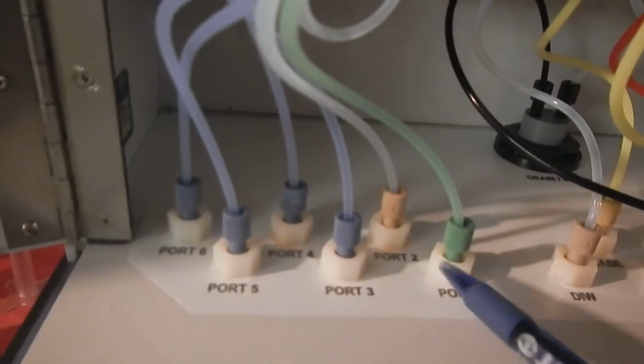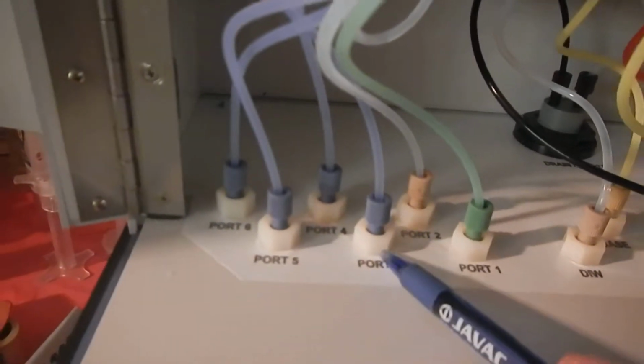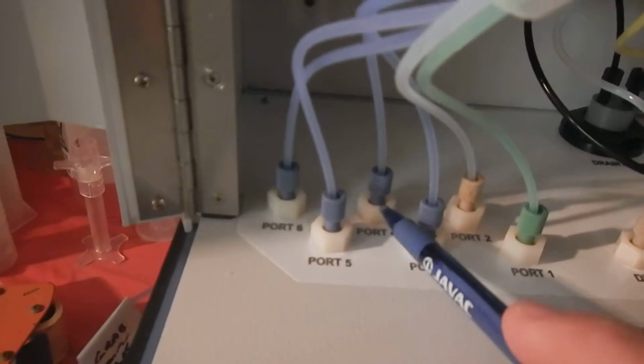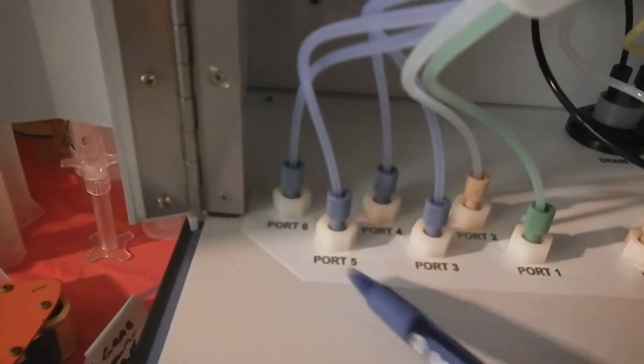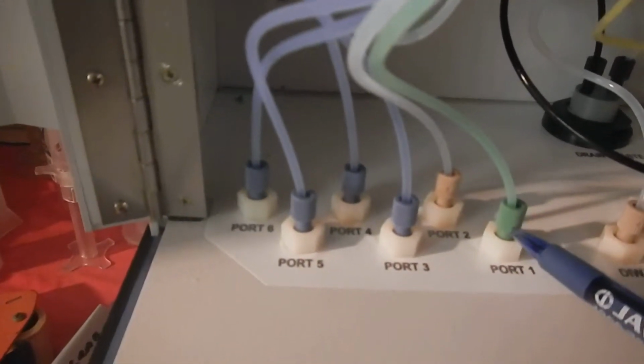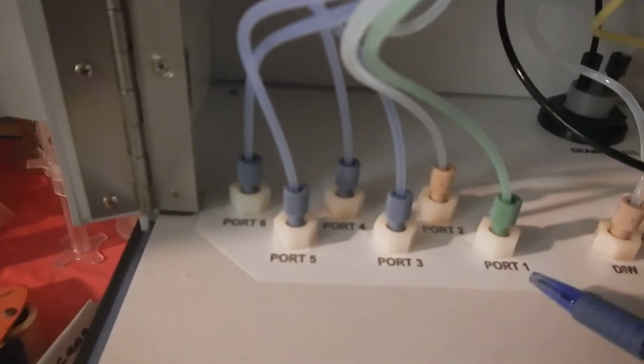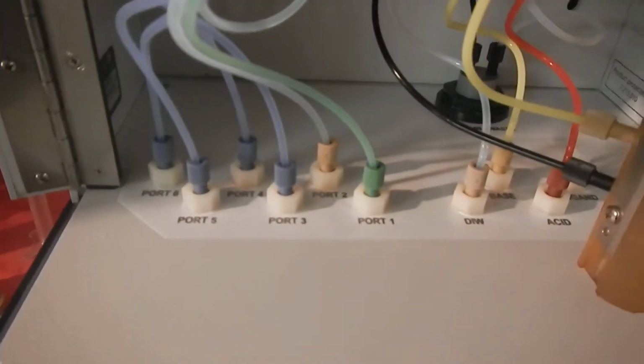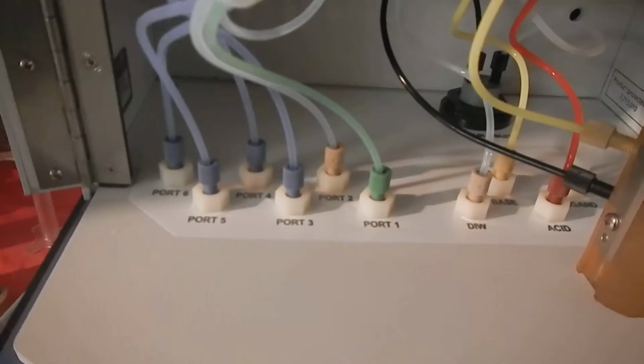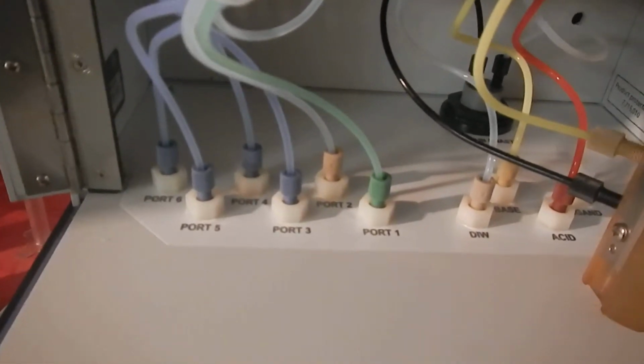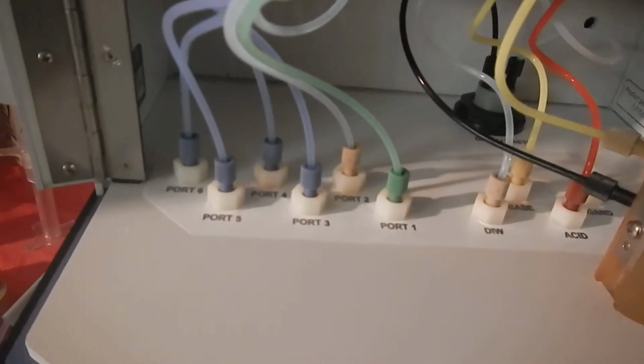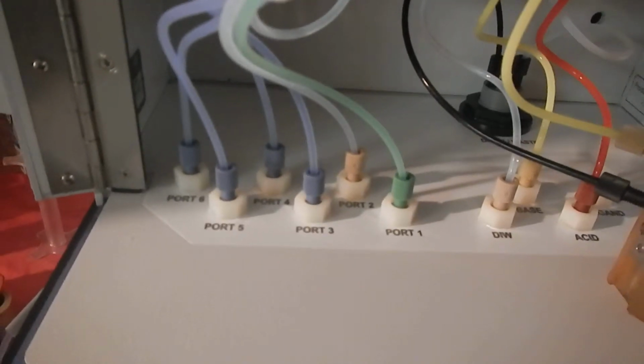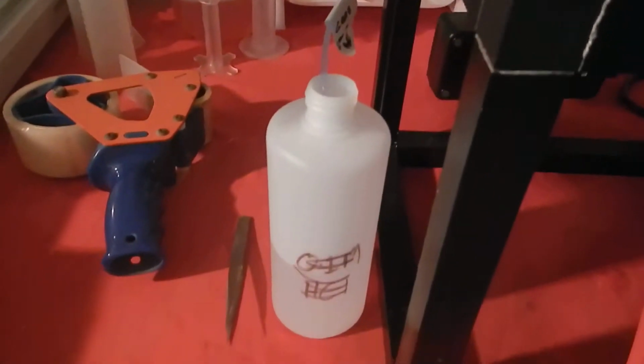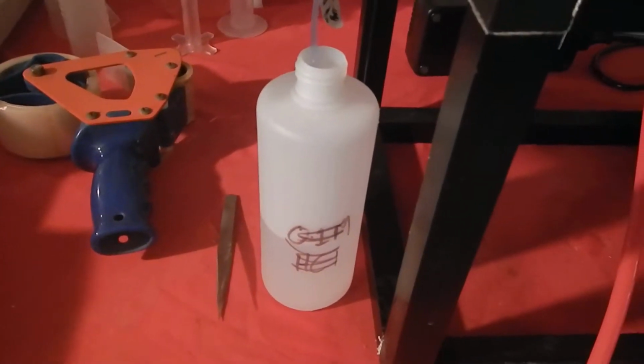Port 1 is standard 1, port 2 is standard 2, port 3 is sample, and in this case port 4 we've got as a grab sample. There are two free ports which can be selected. At this stage we're running a 2 ppm and a 20 ppm calibrant, but we can run anything from low sub ppm levels right through to thousands of ppm on this instrument, on the same machine. It is a very wide dynamic range. I have a grab sample on the side here to be used as an example in a minute.